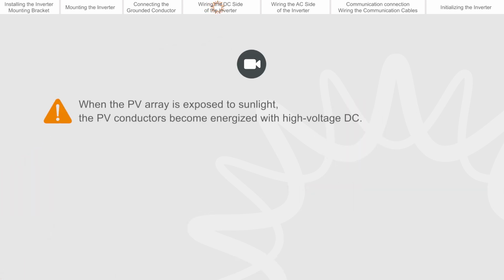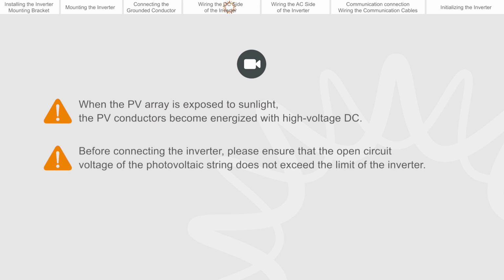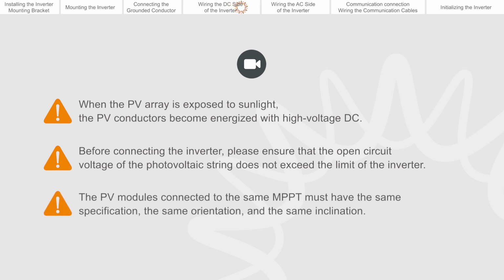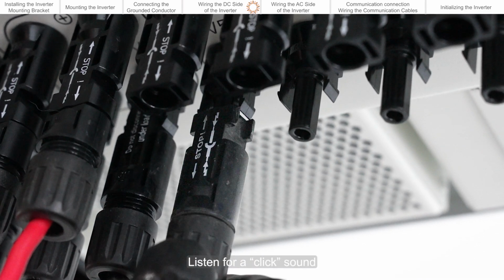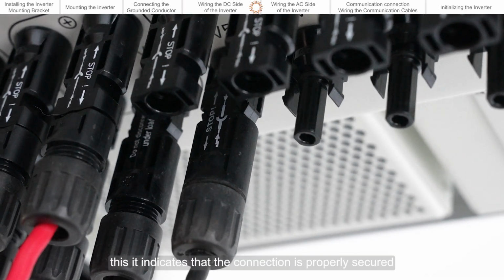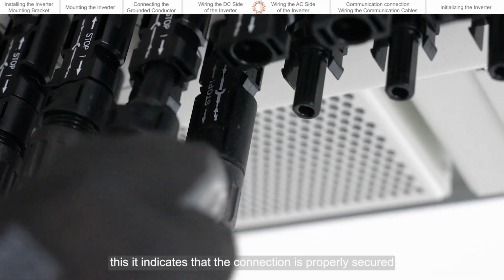When the PV array is exposed to sunlight, the PV conductors become energized with high voltage DC. Before connecting the inverter, please ensure that the open circuit voltage of the photovoltaic string does not exceed the limit of the inverter. The PV modules connected to the same MPPT must have the same specification, the same orientation, and the same inclination. Listen for a click sound. This indicates that the connection is properly secured.